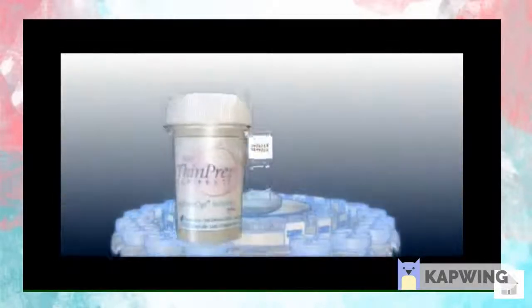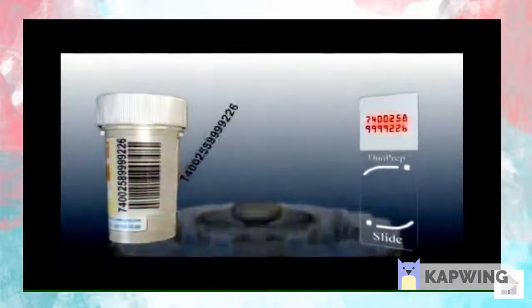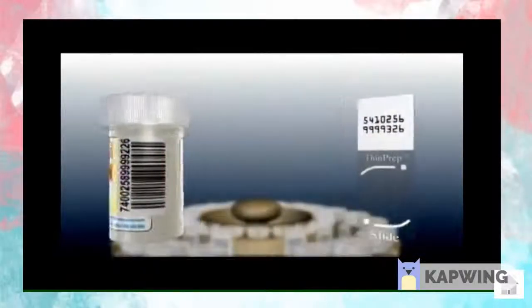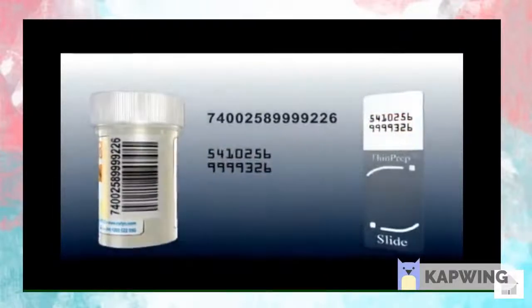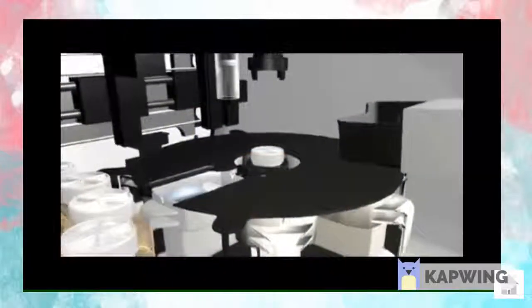Unlike other batch processes on the market, chain of custody verification on the ThinPrep 5000 processor eliminates the possibility of sample mix-up by matching the barcode on the vial with the label on the slide. If the barcode on the slide and vial do not match, the ThinPrep 5000 processor will not process that sample and will move on to the next specimen.